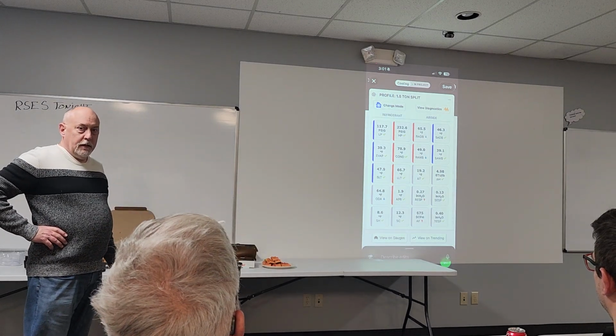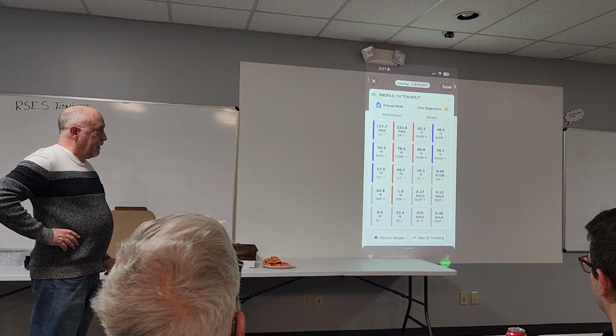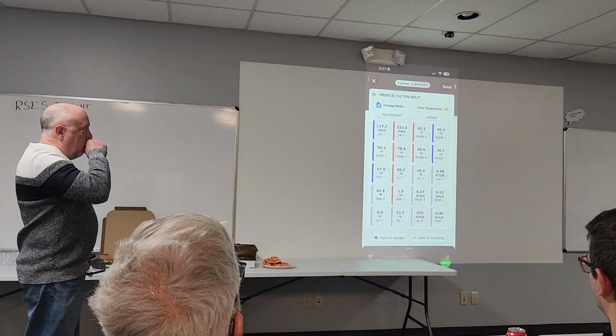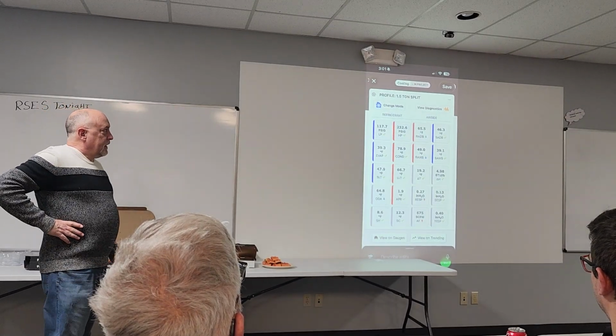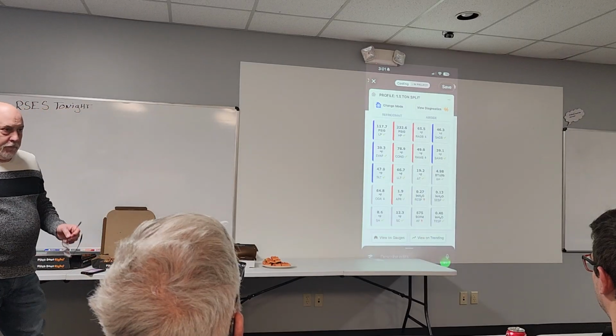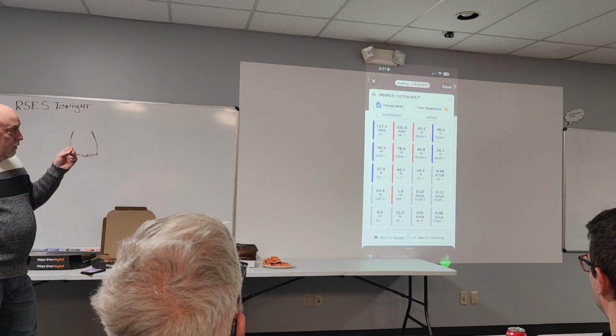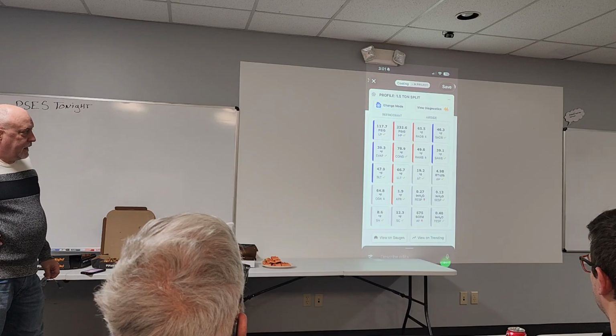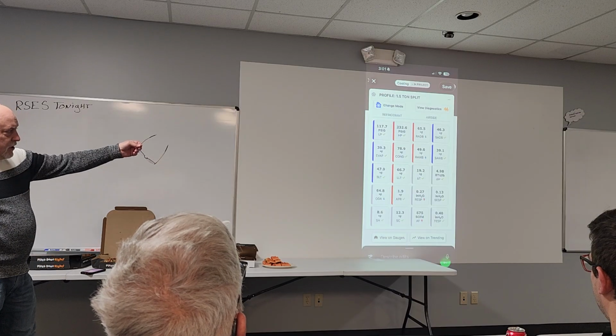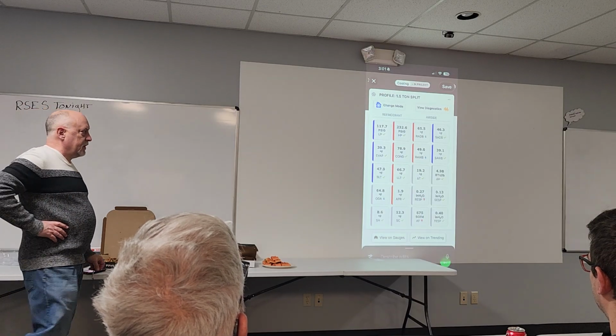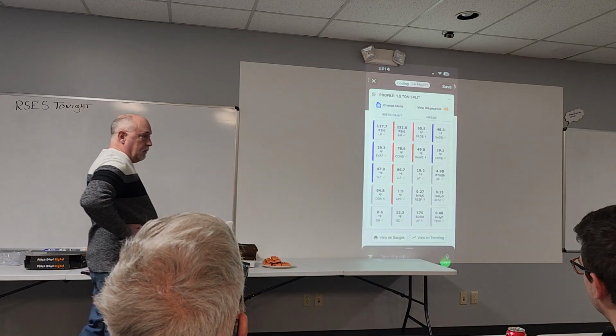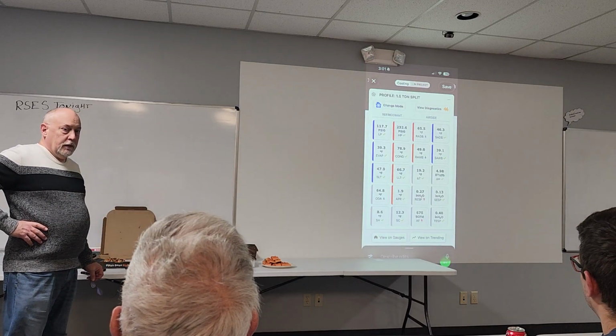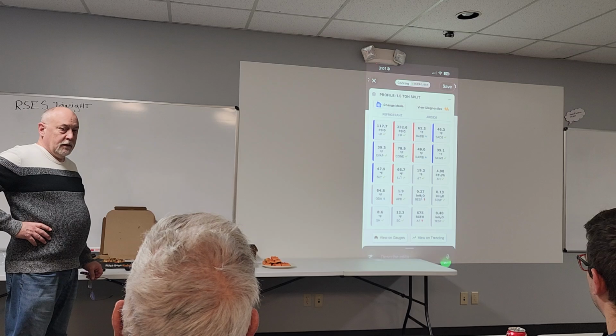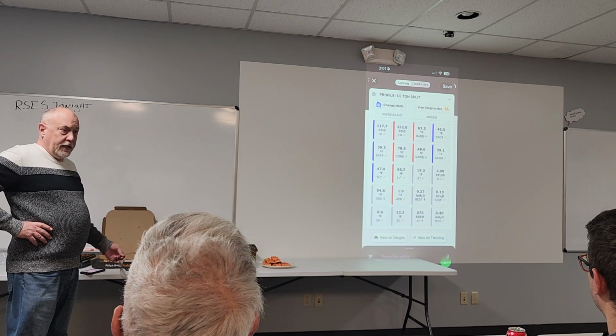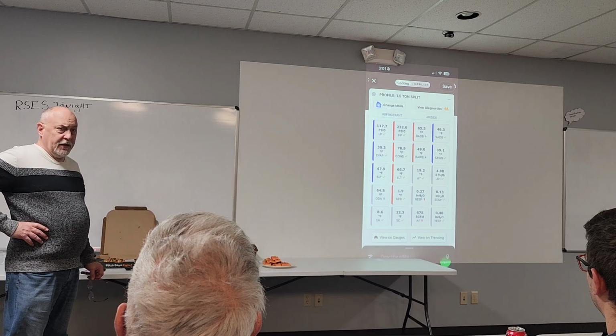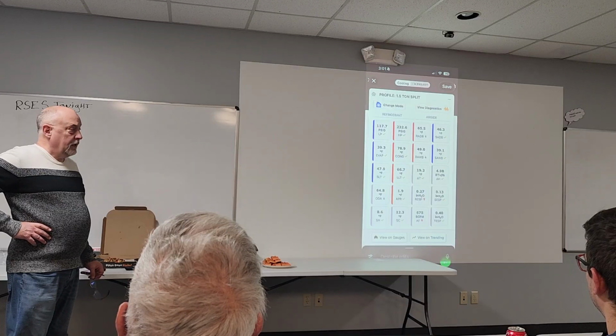Yep, right? Which means you're condensing. Which means I'm condensing, yep. Change in enthalpy is low, but that doesn't surprise me. Just at a glance there, what's a good reason, a couple of reasons we'd have low change in enthalpy? Enthalpy is total heat removed, so that's your heat and humidity. So maybe not much moisture removal. That's right, yeah, it's dry, we're in a shop out there, it's dry, there's not much moisture removed, that's one thing.